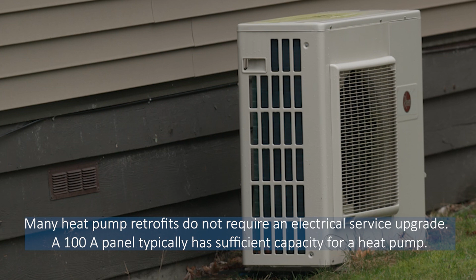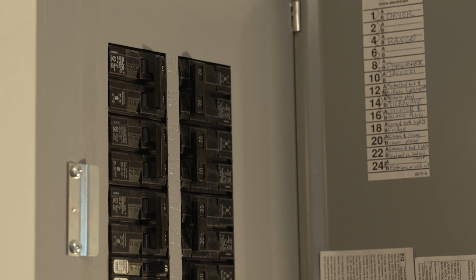There's typically room on a 100 amp service for a moderately sized heat pump system, even allowing the safety factors required by the Canadian Electrical Code, especially if load control options that are allowed by code are adopted. But many contractors default to recommending an upgrade, which can run anywhere between $3,000 to $12,000. Rebates and incentive programs typically won't cover these costs, so it can be a major reason why people don't go ahead with a retrofit. So when you're in this situation, you don't want to be guessing or paying for what you don't have to. It's important to figure out what you need.